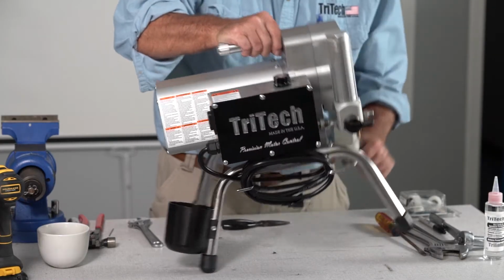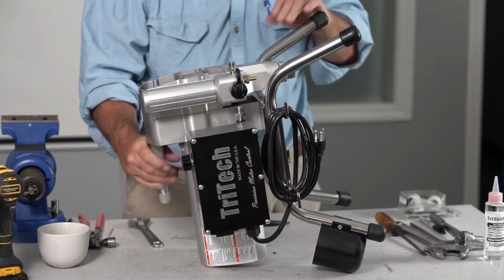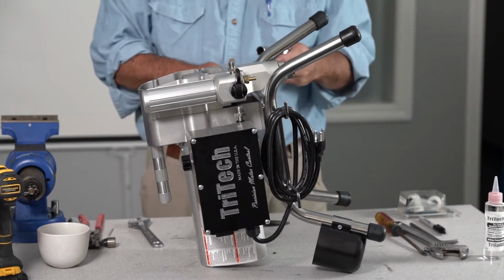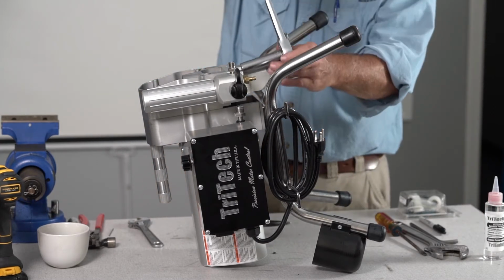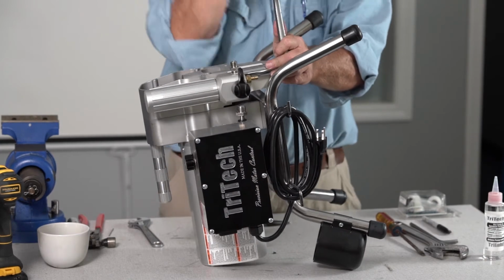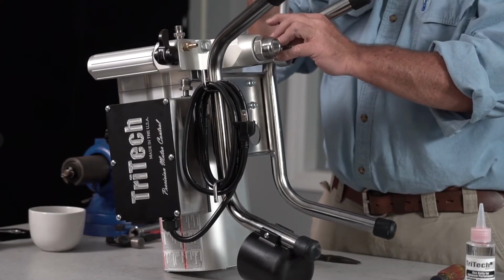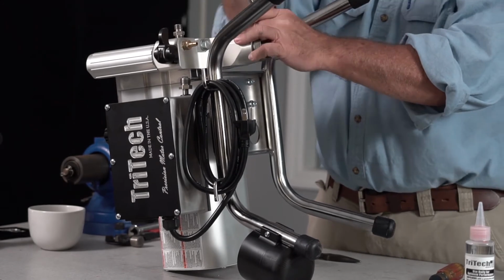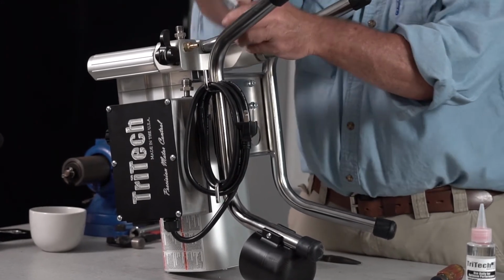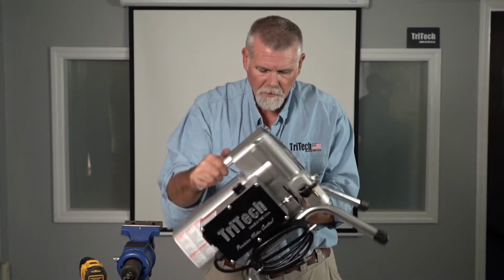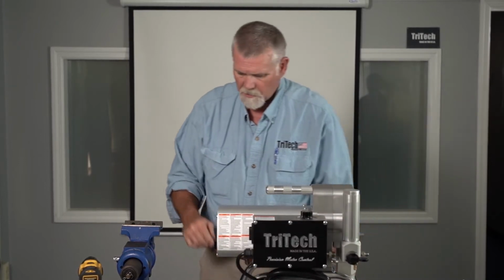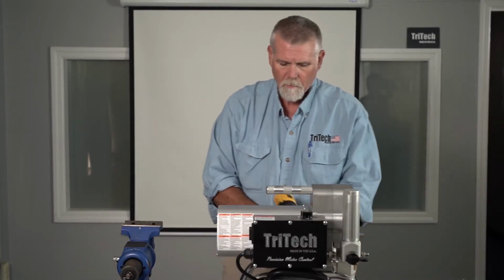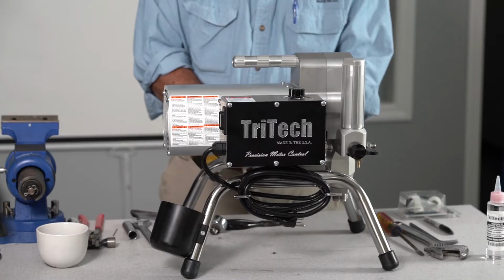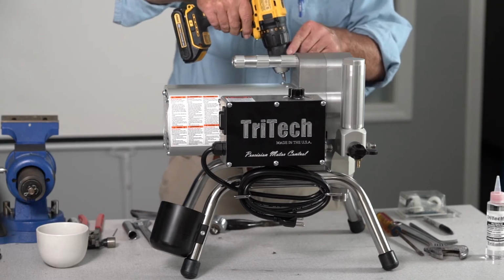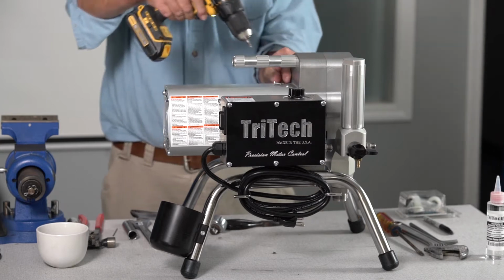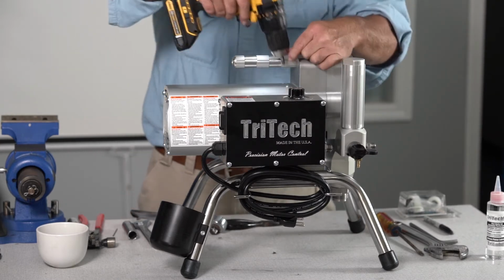Next thing we want to do is put the pump on its back. And then we use a 5/8 socket. And we want to remove the mounting bolts. Then we're going to turn the unit back on its legs and we're going to remove our motor housing. The reason we do this is it just makes taking the fluid manifold on and off a lot simpler.